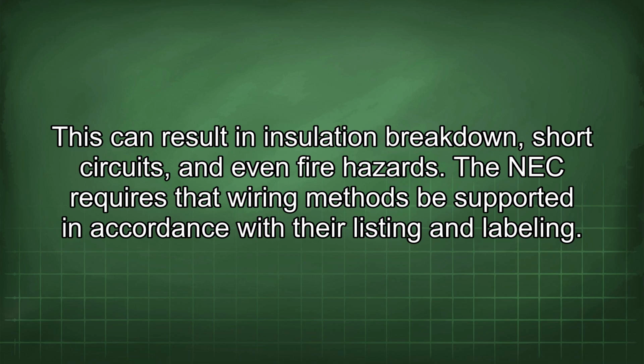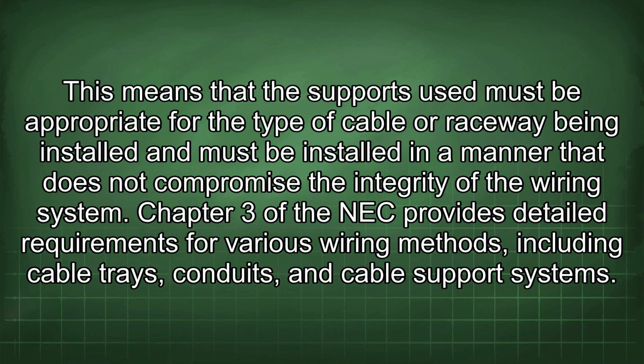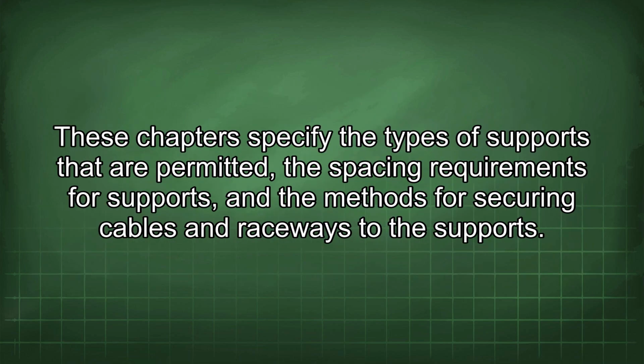The NEC requires that wiring methods be supported in accordance with their listing and labeling. This means that the supports used must be appropriate for the type of cable or raceway being installed and must be installed in a manner that does not compromise the integrity of the wiring system. Chapter 3 of the NEC provides detailed requirements for various wiring methods, including cable trays, conduits, and cable support systems. These chapters specify the types of supports that are permitted, the spacing requirements for supports, and the methods for securing cables and raceways to the supports.